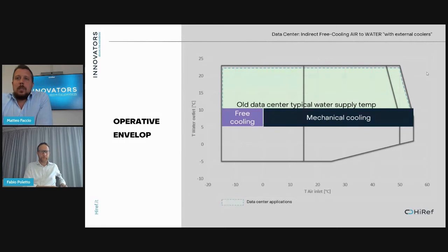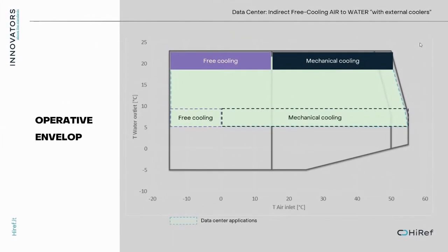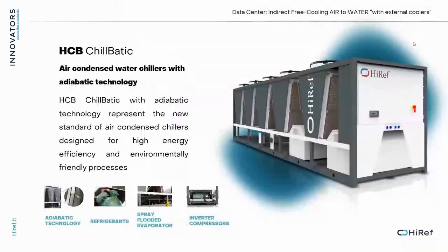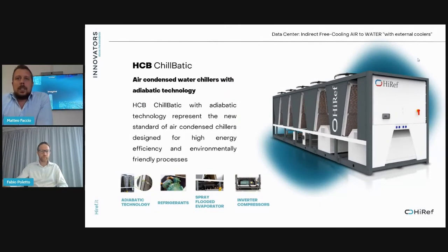Here we can see an example of an envelope of a new type of compressor, which means that we can move the operating area from the standard water production 7-10, let me say, in this range, to the new type 20-25 as a cooling production. We can also see in this graph the possibility to extend the availability of free cooling, not anymore, I would say, below 0, but we can say below 15 ambient, we can keep on using free cooling. Of course, if we integrate the adiabatic system into this kind of unit, so again, a new type of refrigerant, a new type of compressor, and the adiabatic technology, we can still increase the amount of hours that the unit is able to run without the compressor.